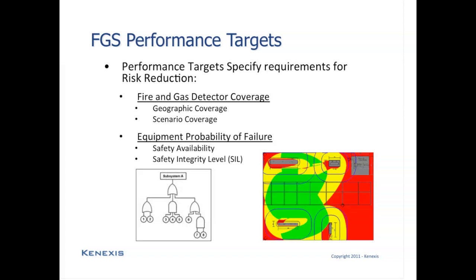Scenario coverage is what we're going to use when we perform a completely, fully quantitative fire and gas system analysis. For scenario coverage, we are literally going to calculate the magnitude and location of every gas release scenario and every fire scenario that could occur in a zone. And then for each one of those literally tens of thousands to hundreds of thousands of scenarios, we're going to determine, one at a time, whether there is one detector, two or more detectors, or no detectors that can actually see that scenario.